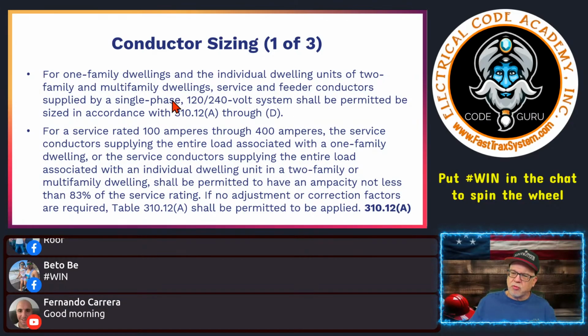All right, so we get to use 310.12 A through D. And it says for a service rated 100 amperes through 400 amperes, so that's another caveat in 310.12. It has to be a rating between 100 and 400. And it says the service conductor supplying the entire load associated with the one-family dwelling, or the individual dwelling unit in a two-family or multifamily dwelling, shall be permitted to have an ampacity not less than 83% of the service rating. If no adjustment or correction factors are required, then you can simply go to the table and do that. Now, I will show that when we go here.